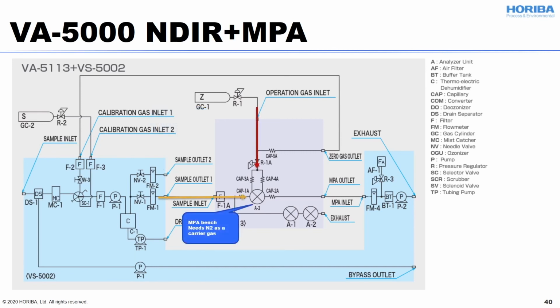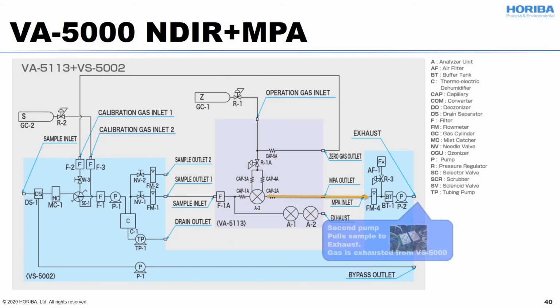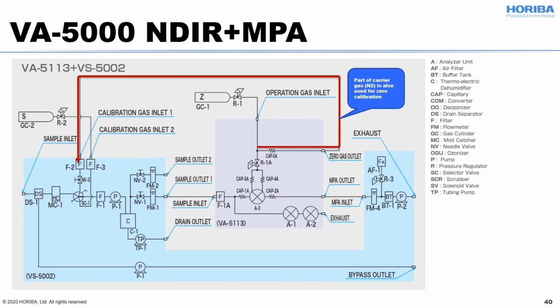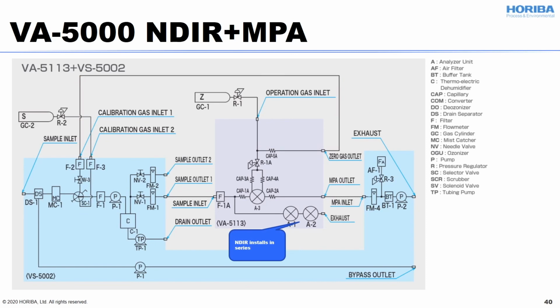And this is the MPA bench analyzer modules right there, which needs N2 as a carrier gas, and the sample gas going out. Here is the second pump, which pulls the sample to exhaust, and gas is exhausted from the VS5000. A part of the carrier gas, nitrogen, is also used for the zero calibration. NDIR is installed in series.